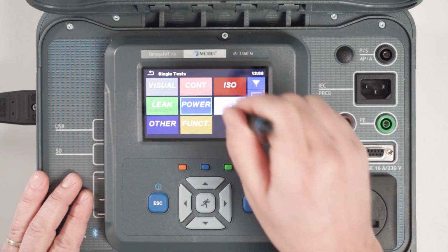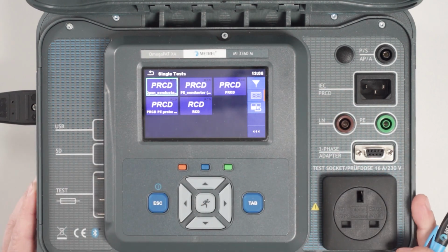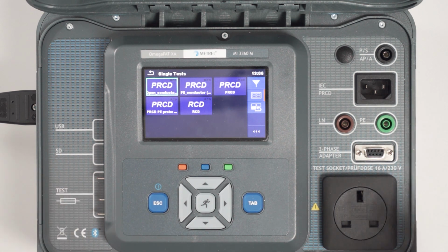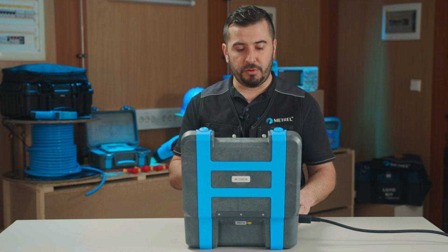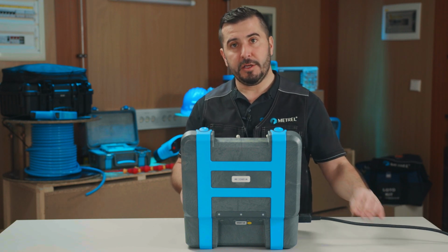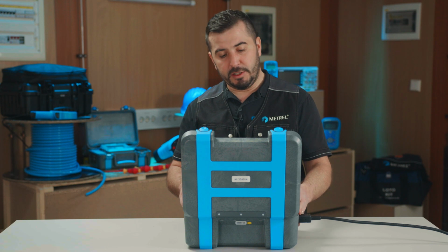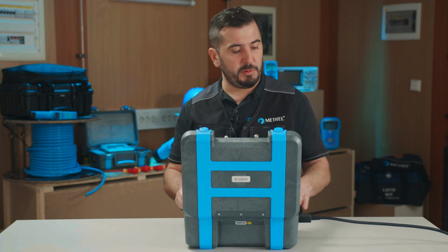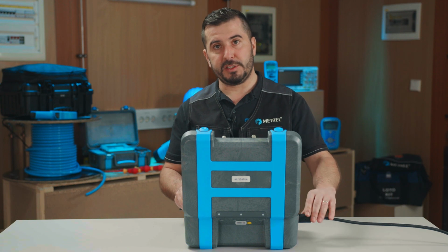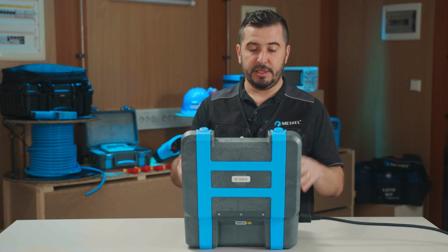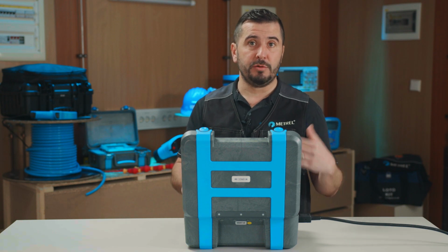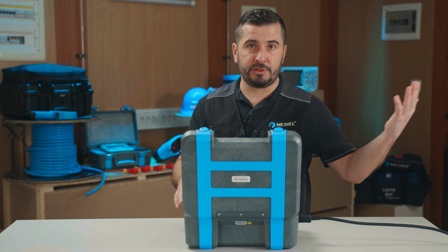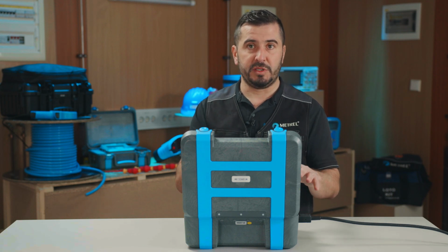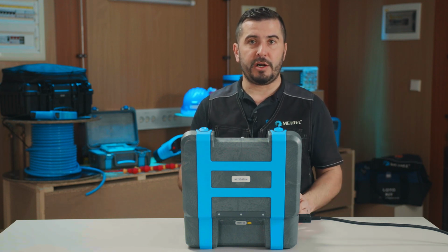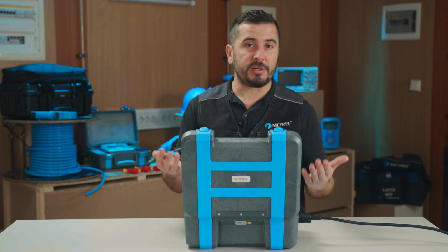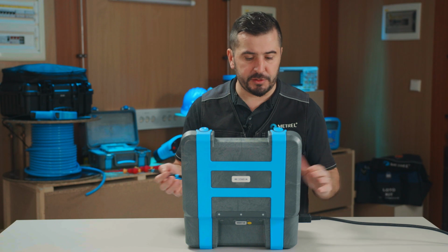And we have the RCD module here, which is applicable to test all sorts of portable RCDs, but we can also test an RCD of our mains installation. In that case the RCD test will be performed from the instrument's mains plug to the installation RCD. The instrument is battery powered, so in case we trip out the mains RCD, the instrument will still be powered on, so we can simply rearm the RCD of the installation and proceed with other measurements if needed.